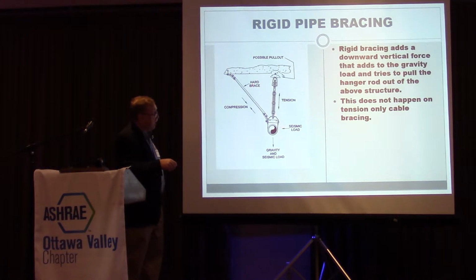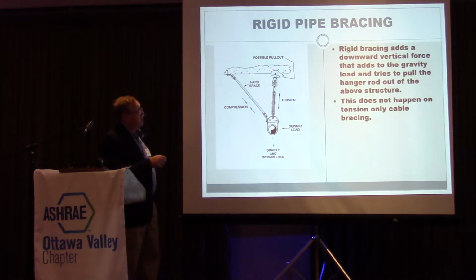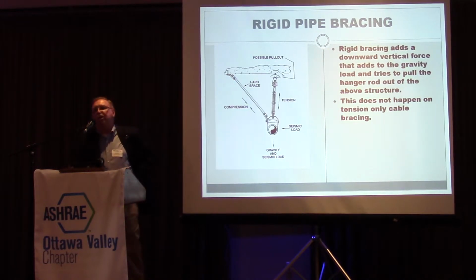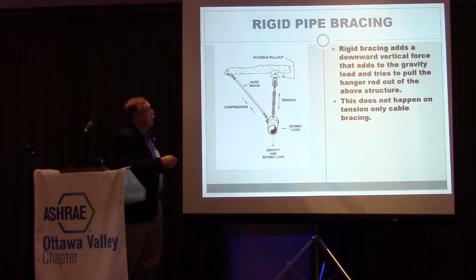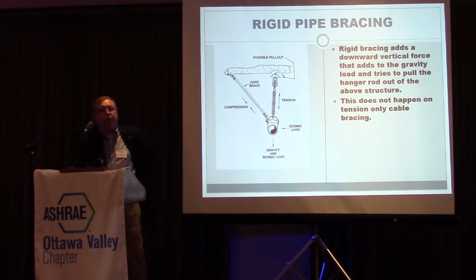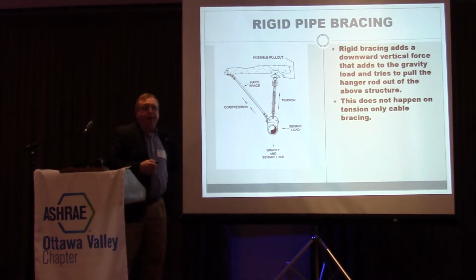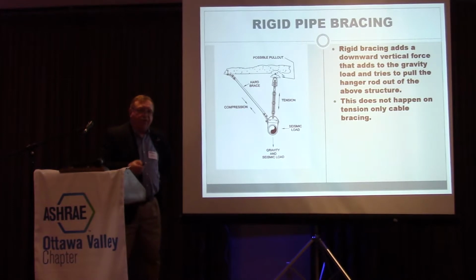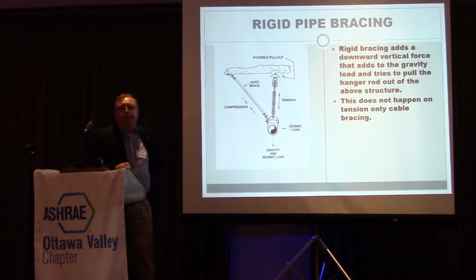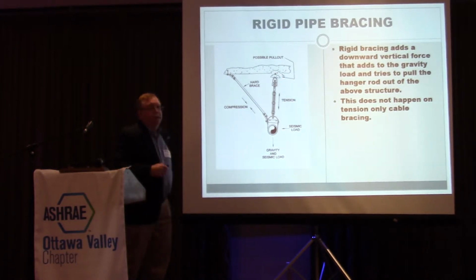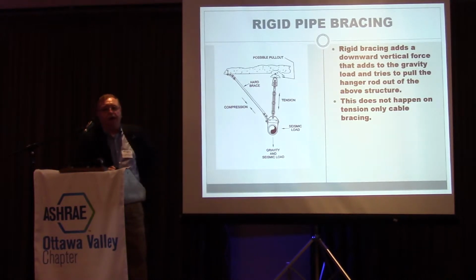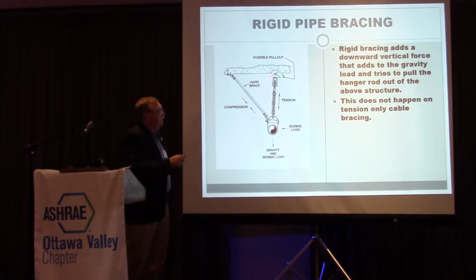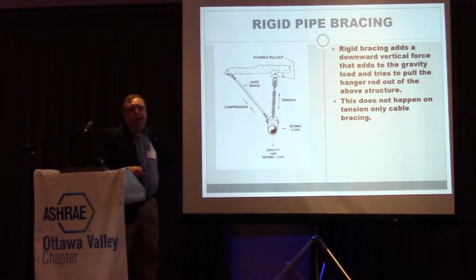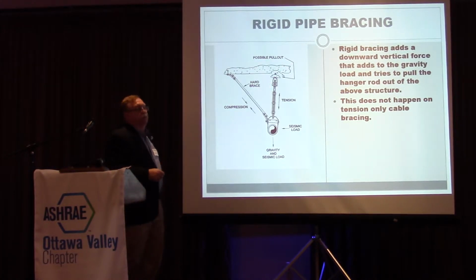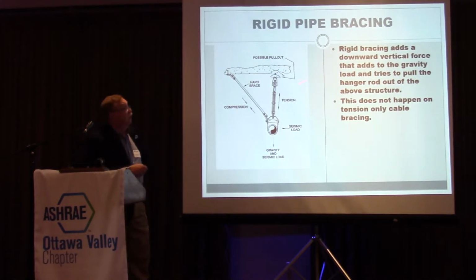This is the runner running, sticking the pole, and then his body going over. So what it does is add a vertical load to the rod holding up the pipe. And what did I just tell you about the anchors that hold up the rods? They're not covered under the seismic requirements. So this is usually an anchor designed for nothing other than the physical weight of the pipe, and now suddenly you've added seismic load to it. We saw many failures of this.